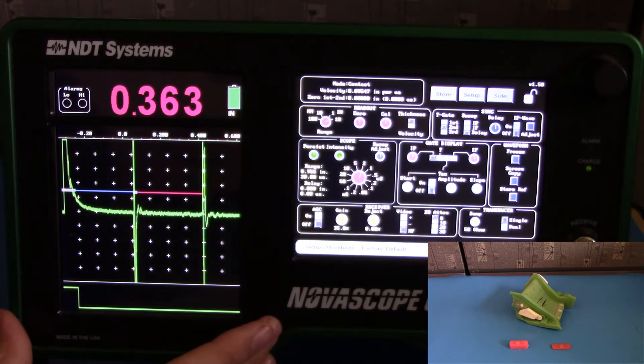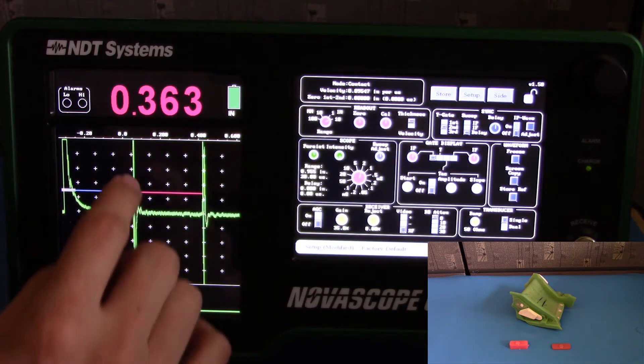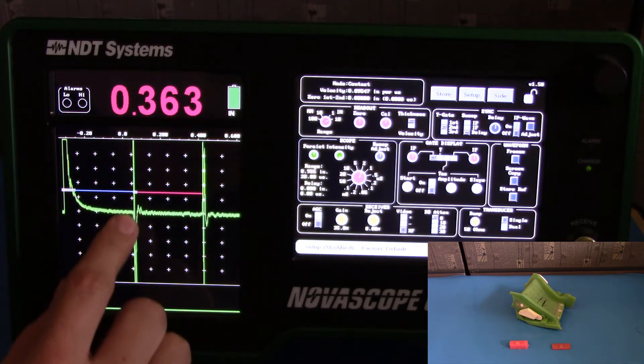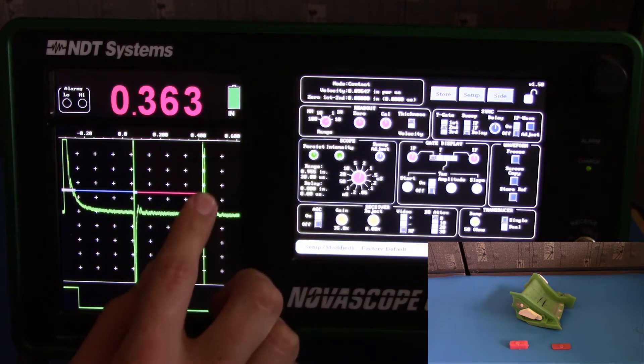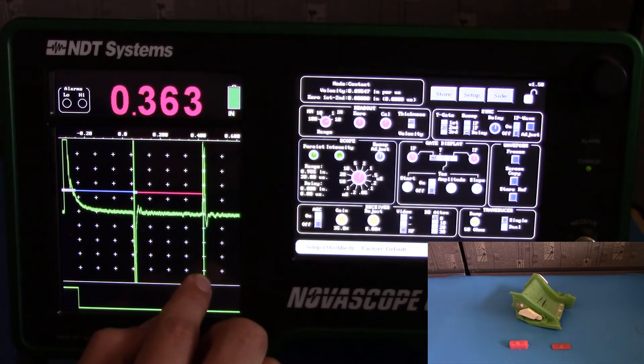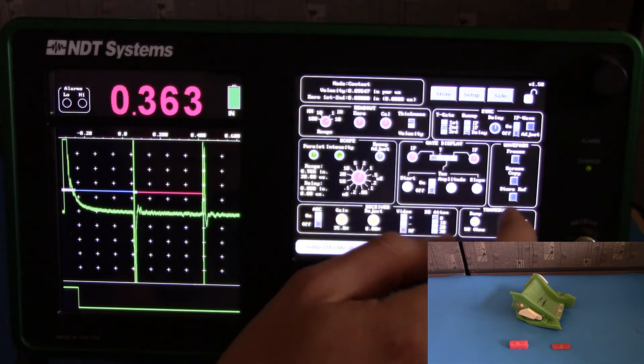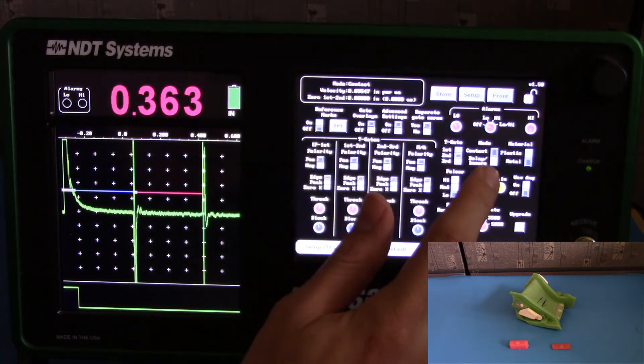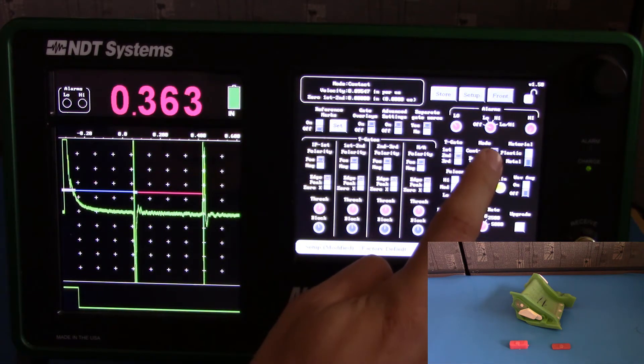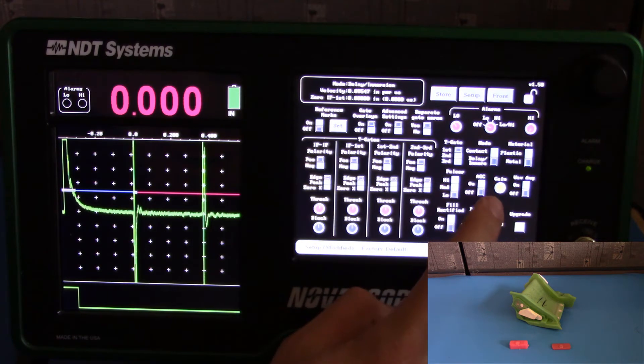We need to set the Novascope up to account for our new echoes. We've got an interface echo where the probe meets the delay line. And we've got a back wall echo, which is the back wall echo from the delay line itself. Go to your side menu. Go to mode. And from contact, hit the switch so that we are in delay immersion mode.